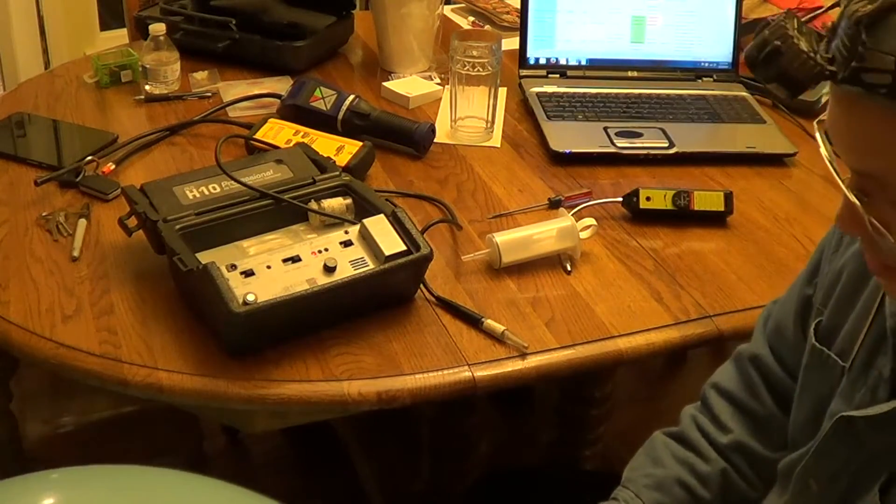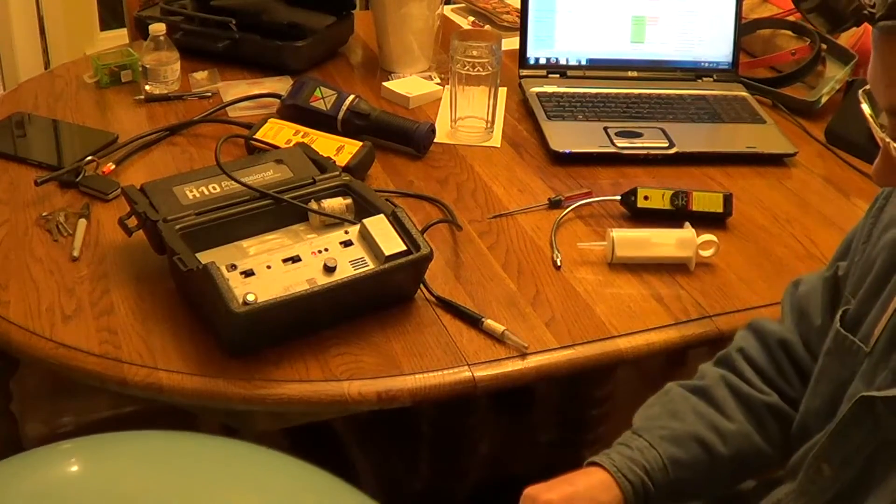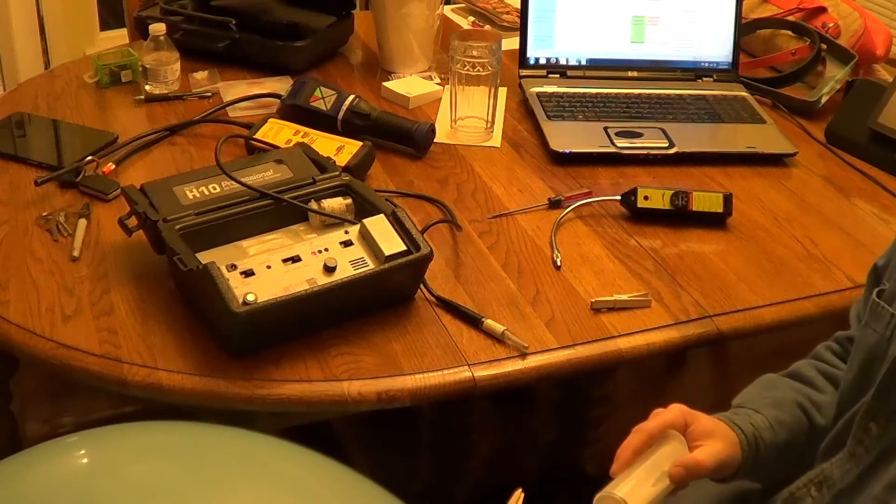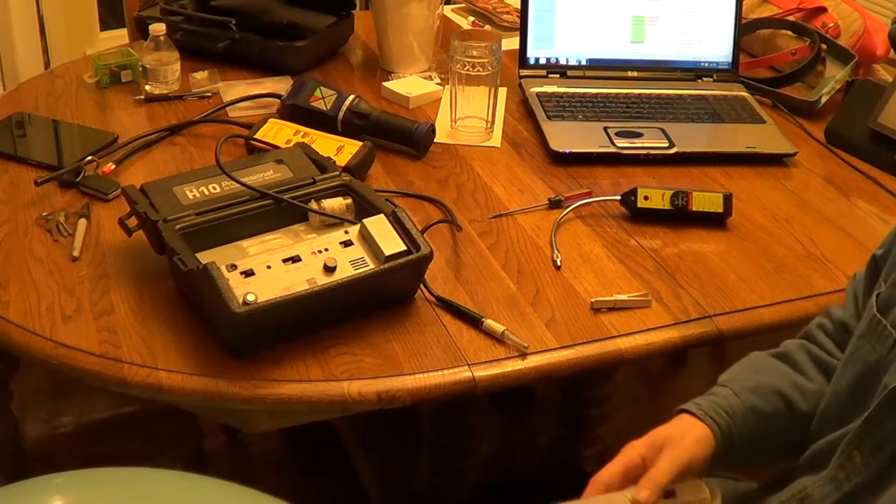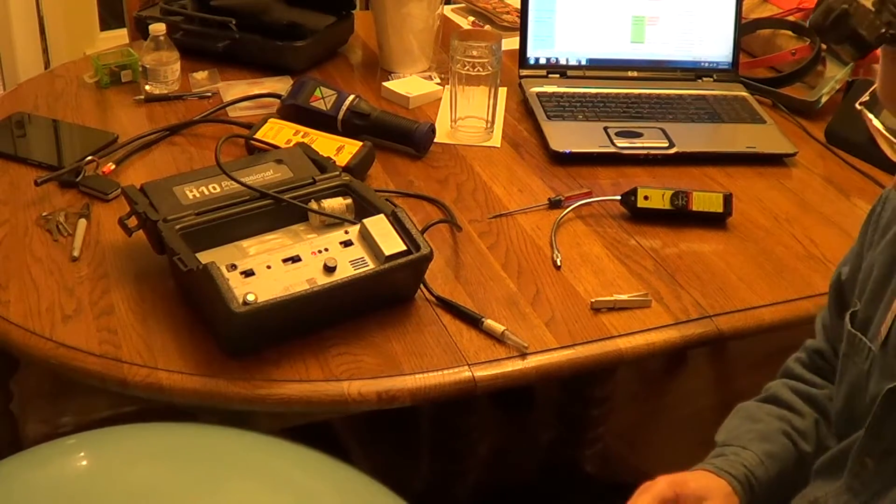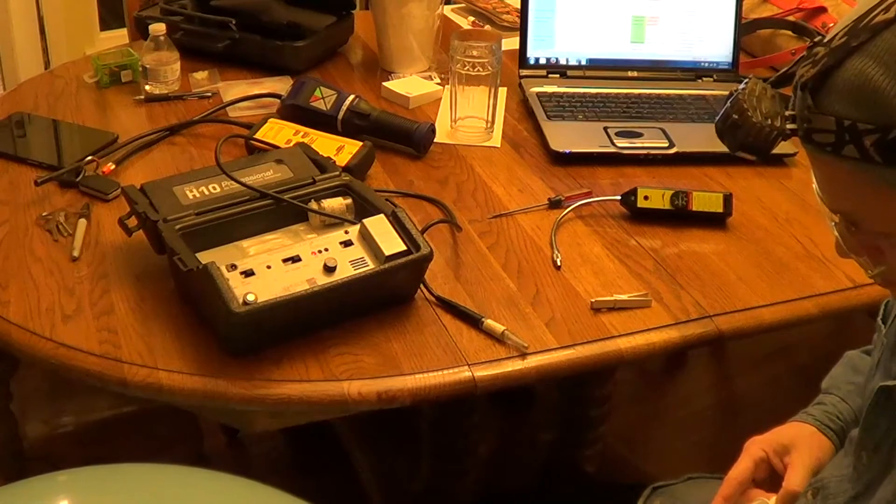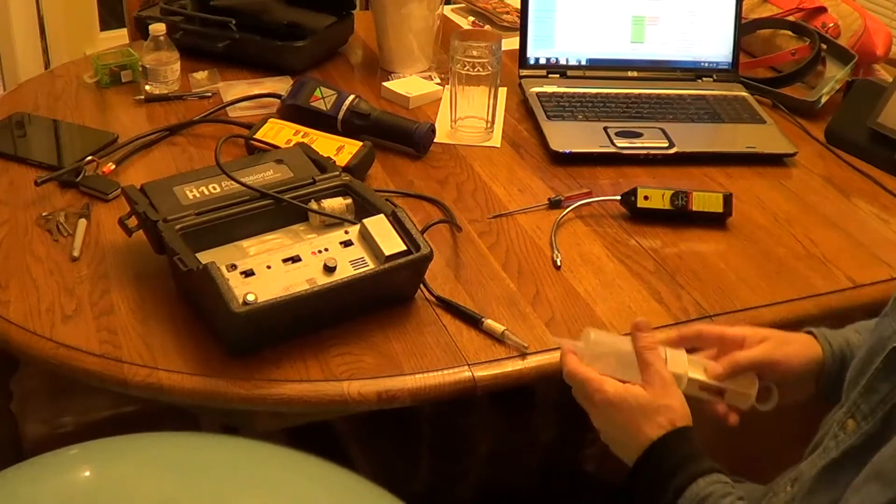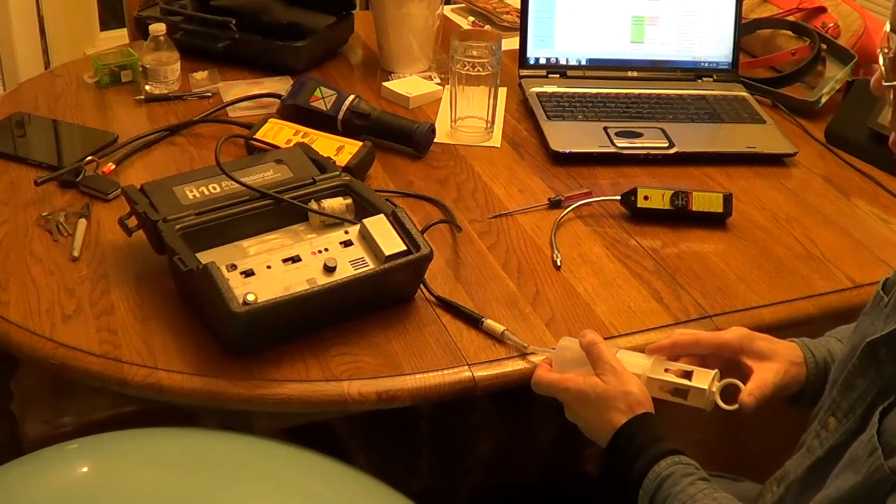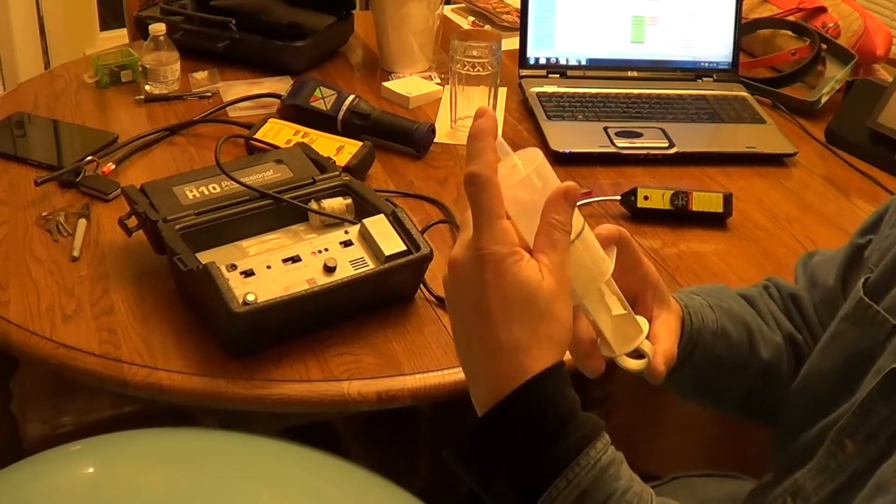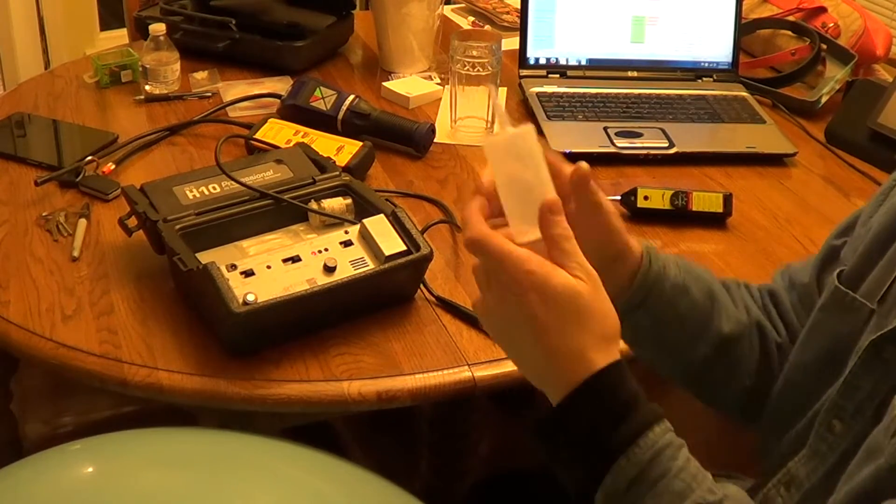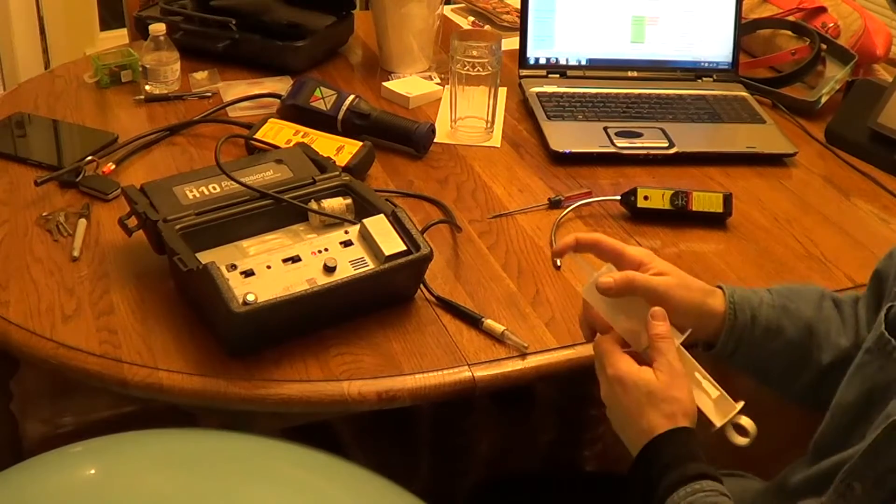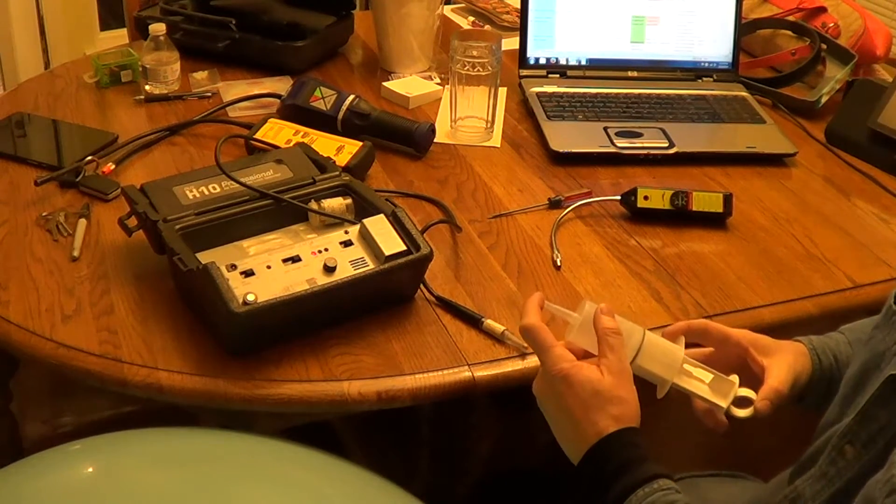Let's do my 10 parts per million. Okay, that's my reference. Actually I'm going to make that again. Okay, we're going to do 10 parts per million R410A. It barely picks it up at 10. Now let's do, actually right now we're at seven. Filling with air, so we're seven parts per million now in my syringe. It barely gets that.